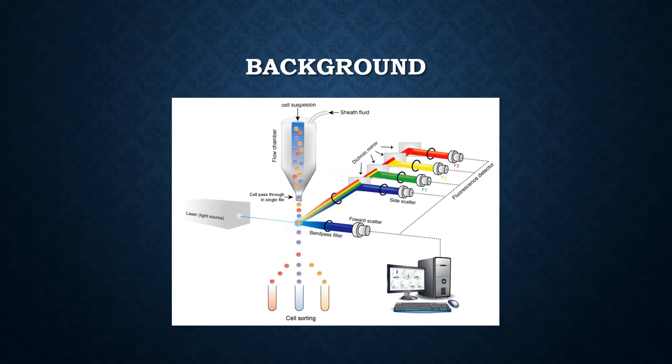So, how does it work? We have the sample placed in the machine. Then the machine takes the sample in and mixes it with sheath fluid. And then the sheath fluid will be guided through a small channel which forms the particles in a line. Then the particles will pass through a laser beam which will be detected by a laser detector.